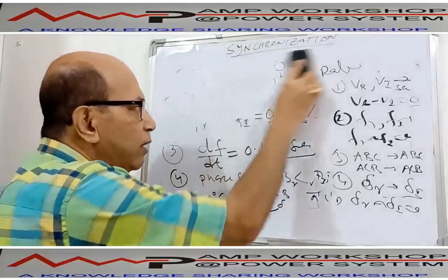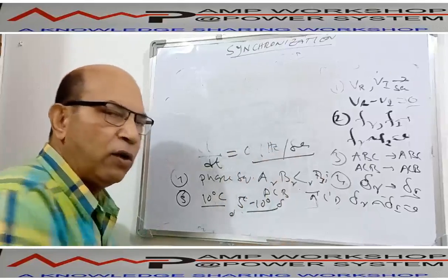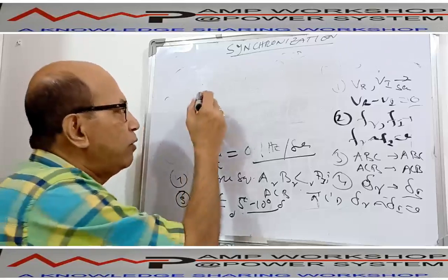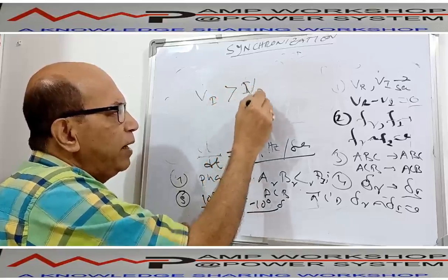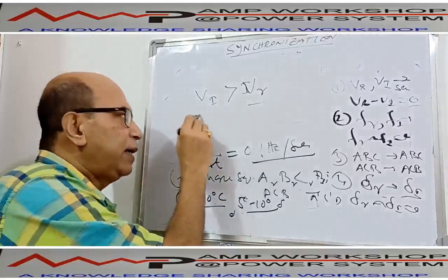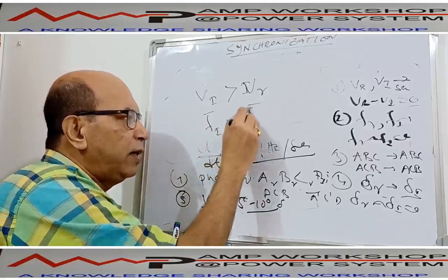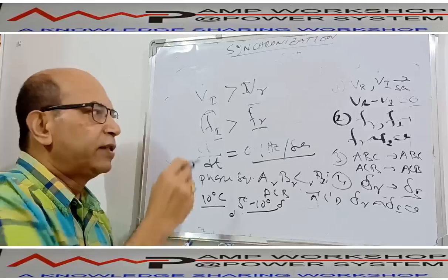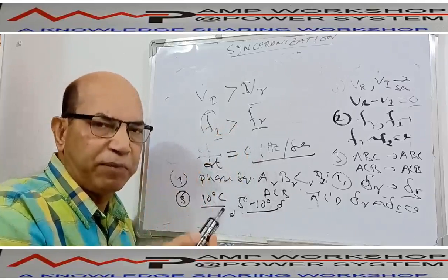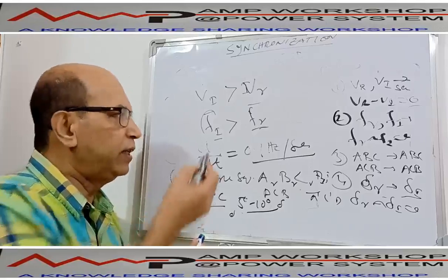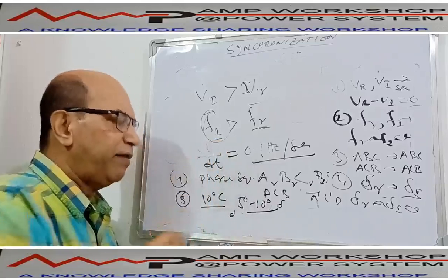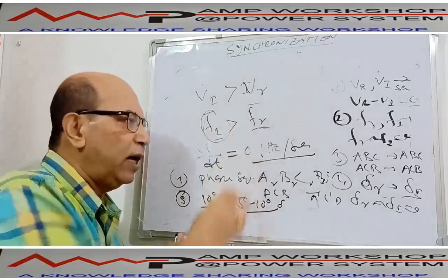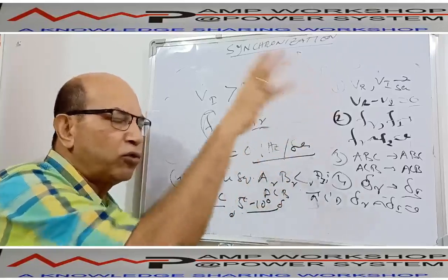In addition, during synchronization, there are two more points required for stable synchronizing operation. Number one: the incoming machine voltage should be slightly more than the running voltage — VI slightly more than VR, maybe within 0.2 to 0.3 percent. Number two: incoming frequency FI should be slightly more than running frequency — maybe 50.2 Hz incoming versus 50 Hz running. If these conditions are maintained, we can successfully close the incoming generator breaker and both will supply the load.